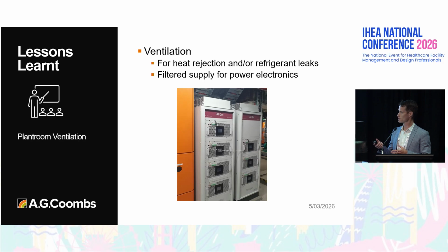These units are the harmonic filters, and they put out a ton of heat, probably 8 to 12 kilowatts per unit. So if that's in an enclosed switch room environment, that's obviously going to be an issue, and we need to address it. And we are seeing more and more power electronics and sensitive equipment going into plant rooms on chillers and controllers and things like that. So filtering the supply air into plant rooms is going to extend the operational life of some of that equipment and prevent the dust building up over time.